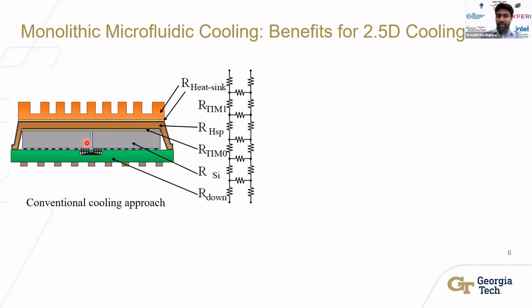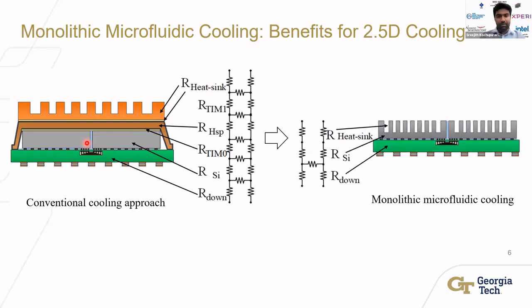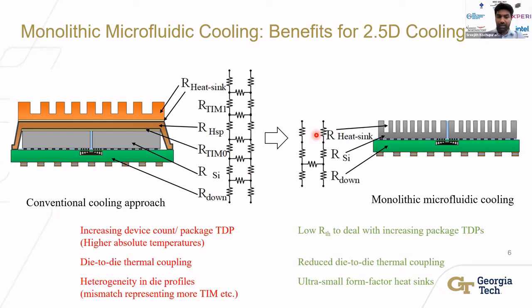Monolithic microfluidic cooling has been proposed for single-die systems. Applying that approach to a 2.5D device — etching heat removal channels directly onto the back side of each silicon die — not only reduces thermal resistive paths but also cuts down thermal coupling paths. This makes monolithic microfluidic cooling a promising technique for 2.5D devices, addressing increased package TDP through reduced thermal resistance while enabling higher compute density.